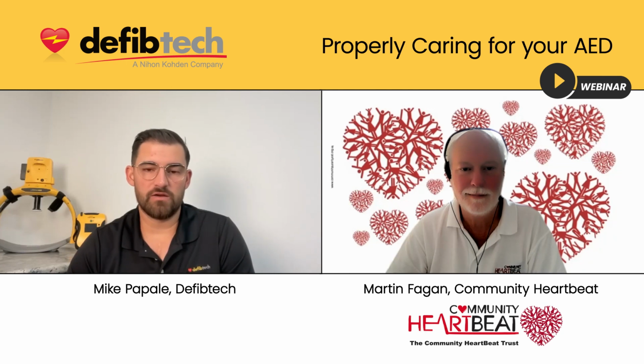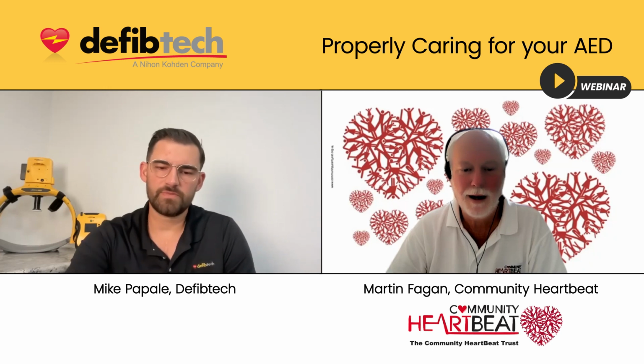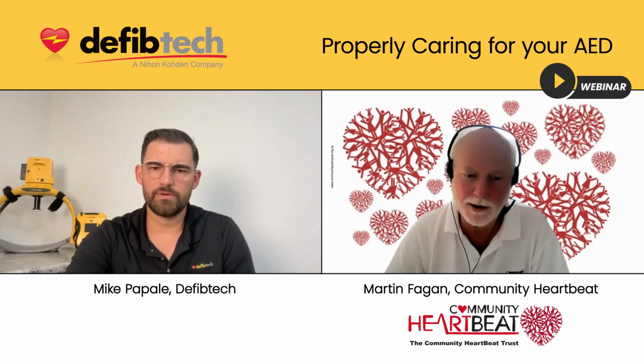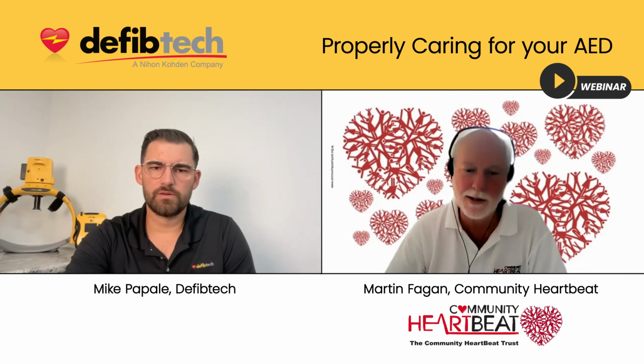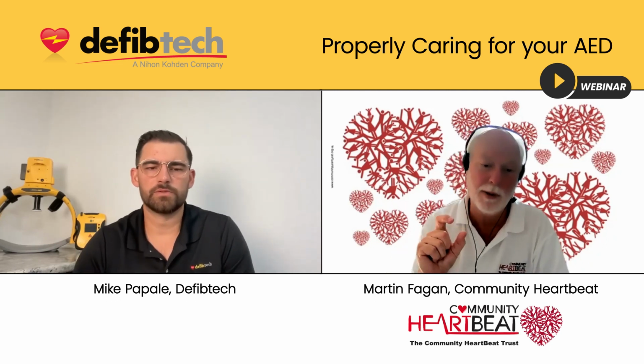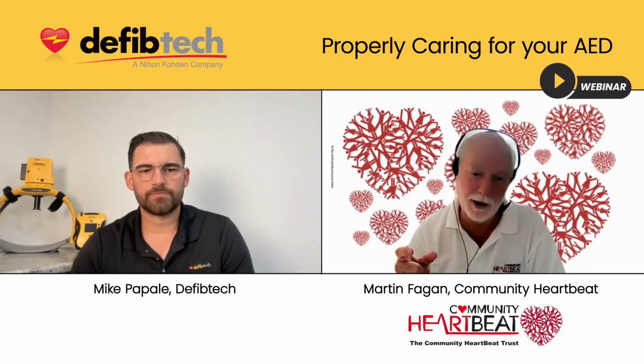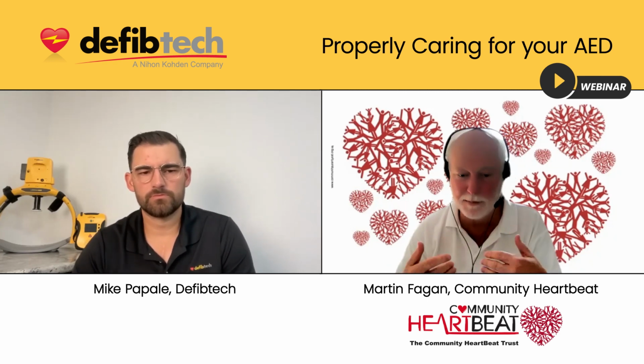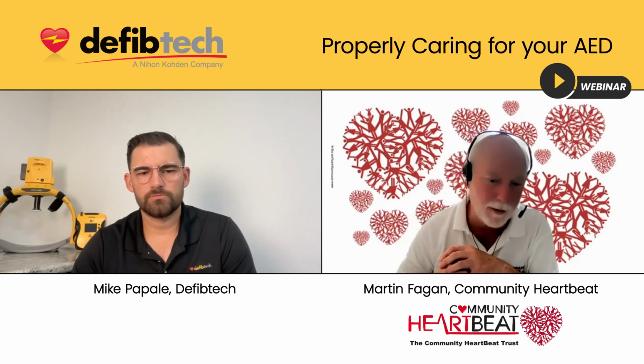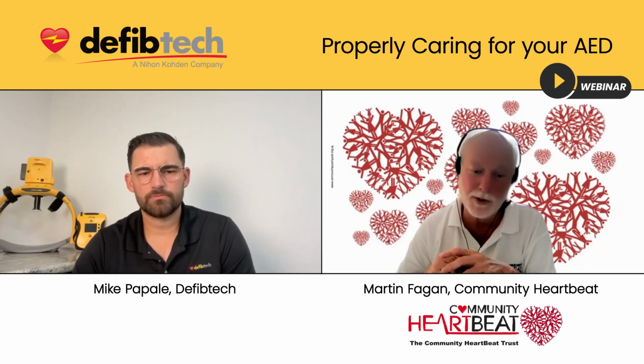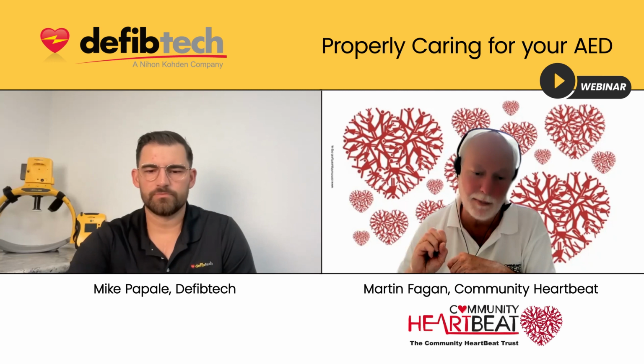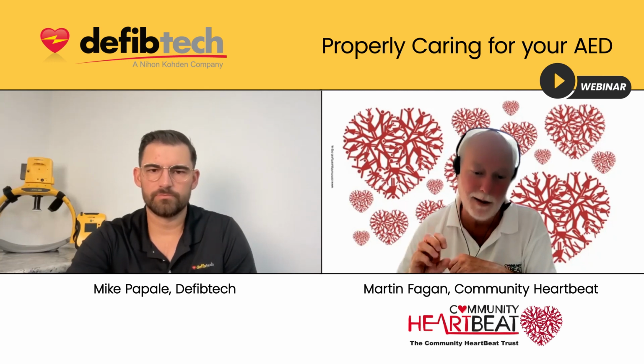The expiration date is there for a reason. You want to make sure you're never in a situation where you have to use expired pads. I think the other thing with modern defibrillators is that they have timing chips in the pads, so that the machine itself knows when the pads are expired. And most machines on the market, with a Defibtech or Zoll or whoever it happens to be, will very irritatingly start beeping and flashing lights at you. And that's using the battery up.